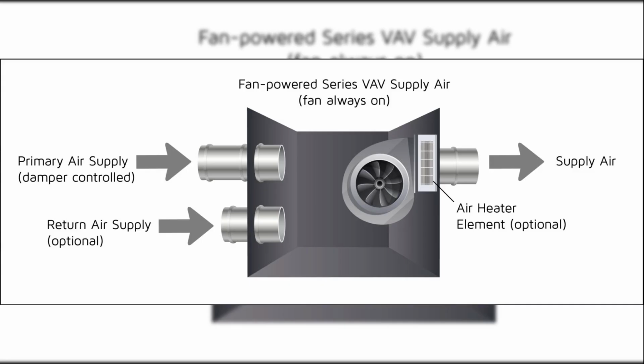Fan-powered boxes, FPB, include a small fan and can be either parallel or series. Parallel FPBs have the fan placed outside the primary airflow, pulling warmer air from the plenum, typically running during heating or deadband modes. Series FPBs have the fan in line with the primary airflow, usually running continuously to deliver air to the space, allowing for downsizing of the central unit.